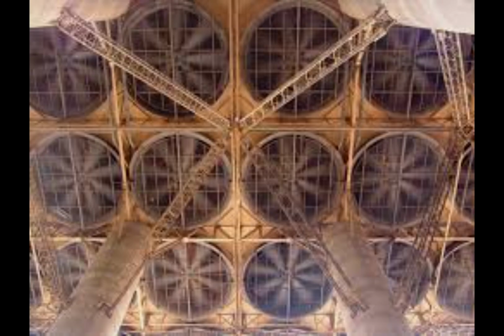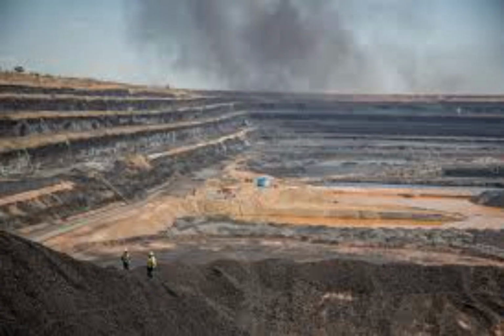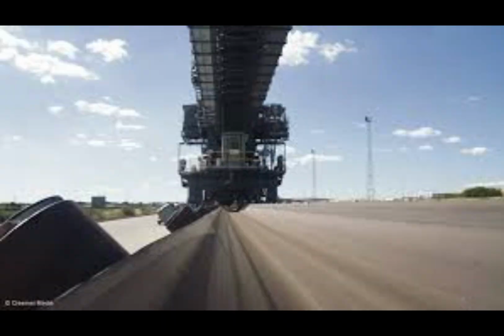Matimba is the largest direct dry-cooled power station in the world. The use of dry cooling technology has considerably reduced water consumption at the plant relative to those using wet cooling systems. Matimba is fueled by the open-cast Grootegeluk coal mine on the Waterberg Coalfield, with about 14.6 million tons of coal a year via a conveyor system. The mine is also contracted to supply the new Medupi power station.